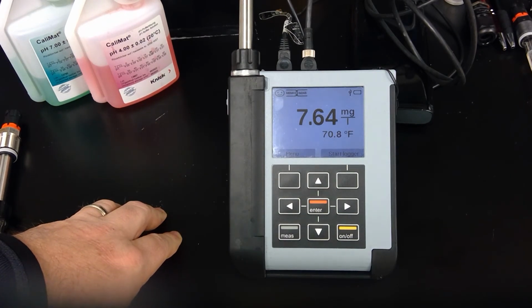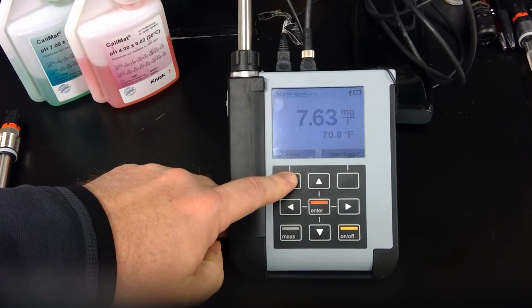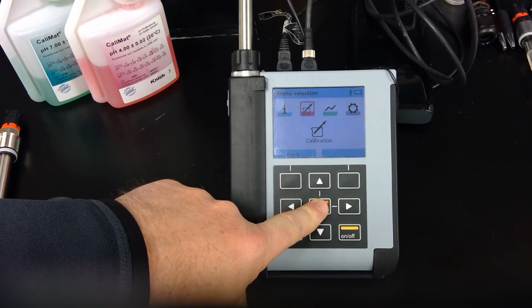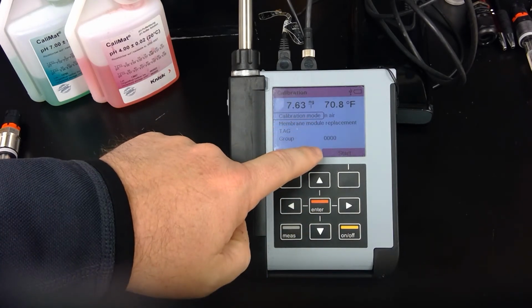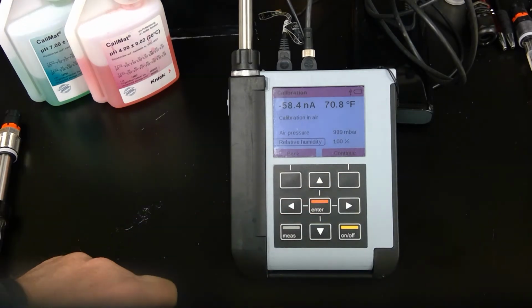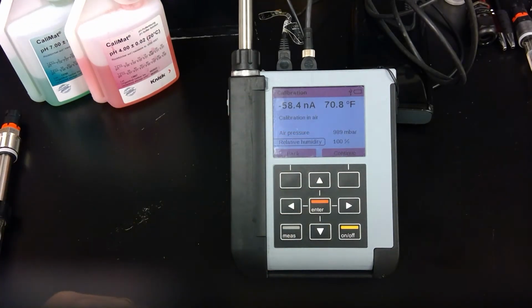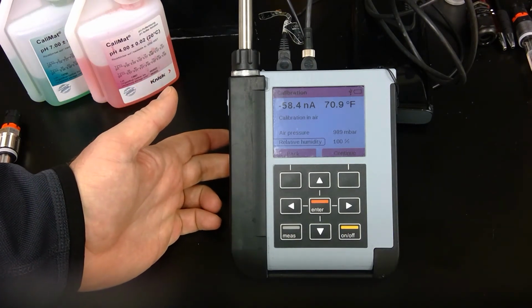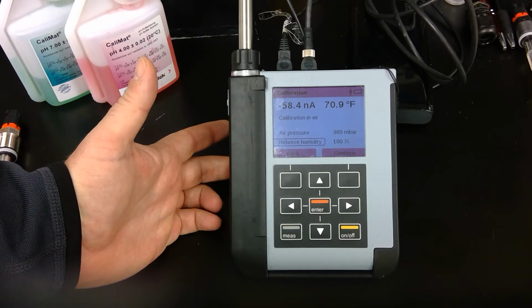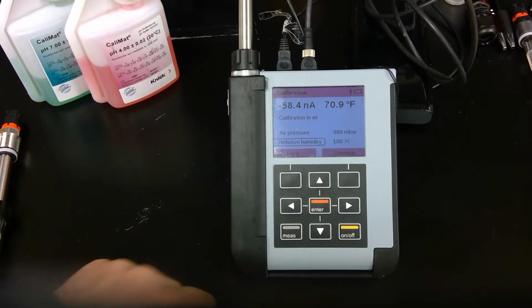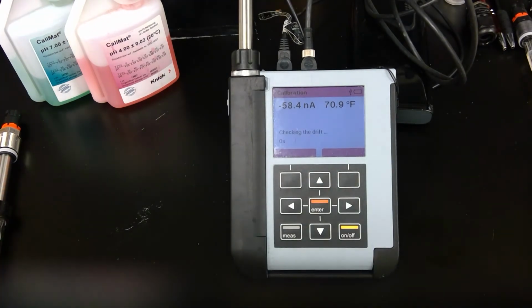So right now we have it set up to go ahead and get started for a calibration. So I hit menu, go to the calibration icon. We're going to do an air calibration. I'm going to hit start. Now if you look here, my air pressure is 989 millibar. That's because there's a pressure device in the Portavo that automatically measures that air pressure, so you don't have to do anything. And then the relative humidity is already set to 100%. So I hit continue. So now this part of the calibration may take 30, 60 seconds, give or take. And once it's completed, we'll go ahead and view the calibration results and we'll apply that calibration to the SE706.